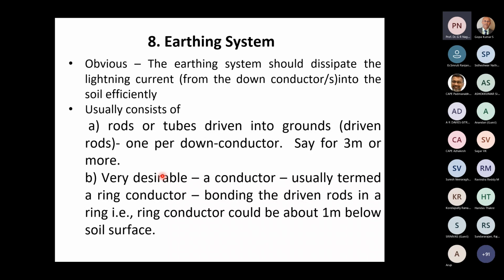There can be horizontal rods or tubes also, but most commonly rods are used, not necessarily tubes. But driven conductors are typically tubes. They are more convenient because they can offer a large cross section. Rods are relatively easy on the horizontal side. Now, very, very desirable, let me emphasize, is a conductor, usually termed a ring conductor, which bonds the driven rods at the bottom in a ring. It could be about 1 meter below the soil surface. It bonds the bottom ends of all the down conductors, forming a conducting ring.